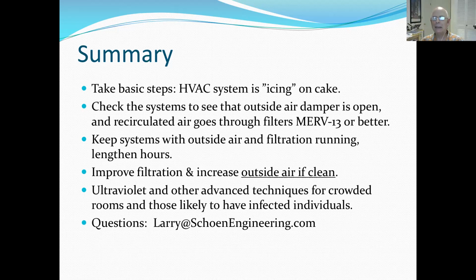The second thing is there's surface contamination and re-entrainment from the surface. This applies less so to a concrete floor, so that helps. But any floor can have re-entrainment, meaning people walk on the floor, and if the larger particles have been directed down to the floor and settled there, then I walk on them, I have the potential to re-entrain them. If it's a concrete floor and you don't have a lot of floor traffic, whether it's people or machines, you have less, but there's some. So, has anybody modeled all of this on your particular room? Probably not. So that's why we use a bundle of control measures, and there's some judgment involved. And looking at your individual facility, as you have done, which is great, you can look at where your risk is appropriate.